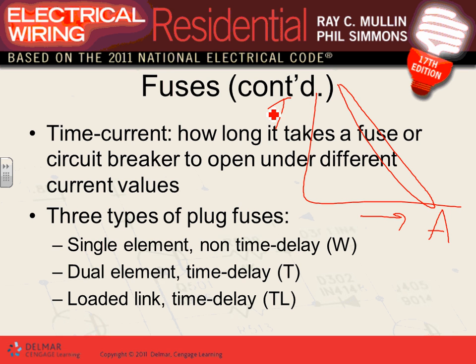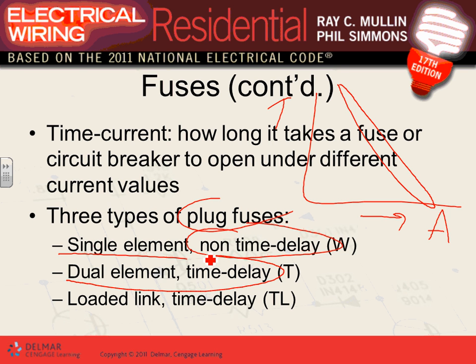There are three types of plug-in fuses: single-element non-time-delay, typically used on feeders; dual-element time-delay fuses, typically used on motors; and loaded link time-delay fuses. You can intentionally delay the trip of circuit breakers or fuses depending on the application.